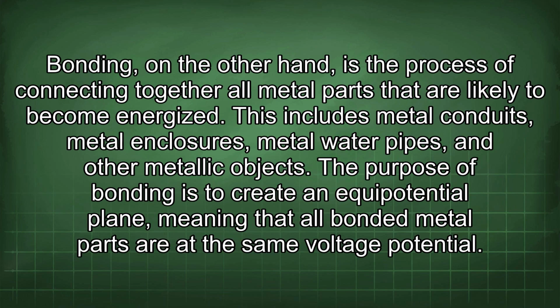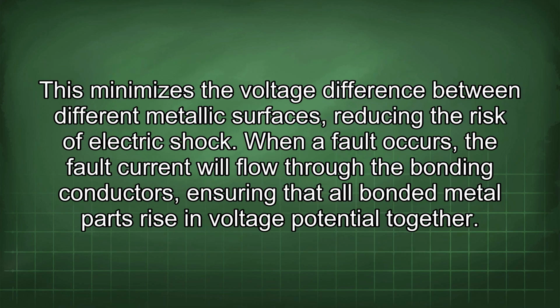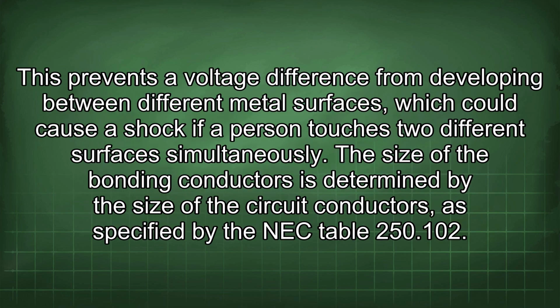Bonding, on the other hand, is the process of connecting together all metal parts that are likely to become energized. This includes metal conduits, metal enclosures, metal water pipes, and other metallic objects. The purpose of bonding is to create an equipotential plane, meaning that all bonded metal parts are at the same voltage potential. This minimizes the voltage difference between different metallic surfaces, reducing the risk of electric shock. When a fault occurs, the fault current will flow through the bonding conductors, ensuring that all bonded metal parts rise in voltage potential together. This prevents a voltage difference from developing between different metal surfaces, which could cause a shock if a person touches two different surfaces simultaneously.